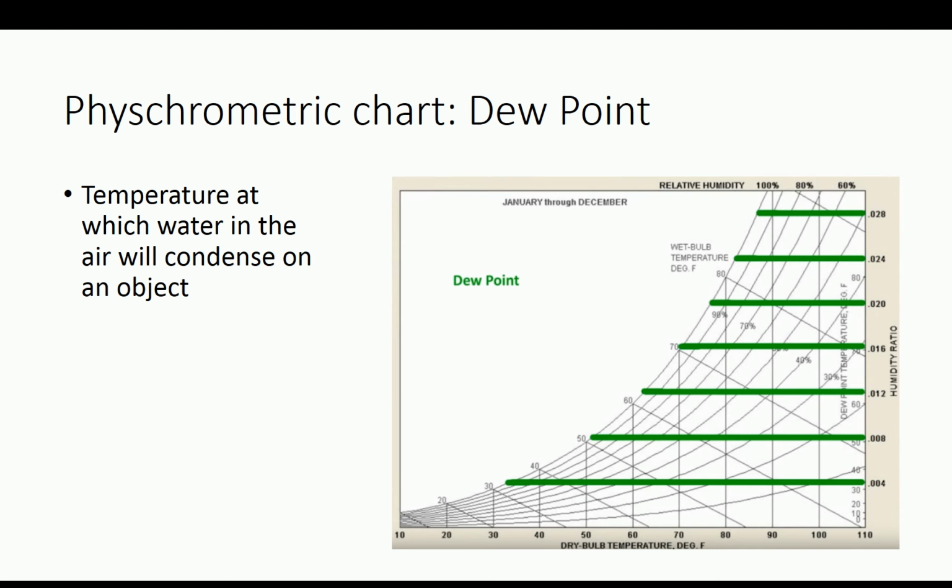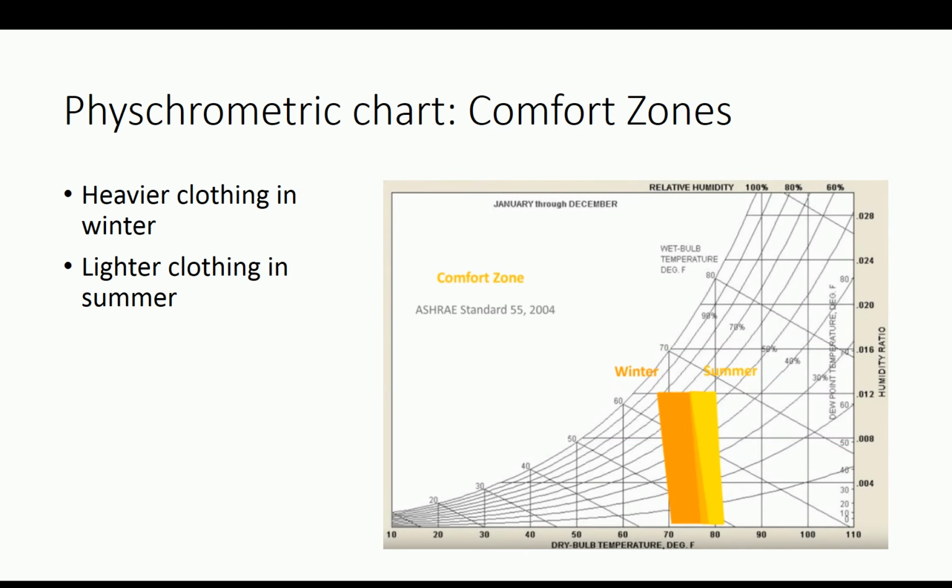Okay? All right, so I mentioned to you guys that we plot all of these things. I also mentioned that we can use the psychrometric chart to plot the comfort zones. So here is an example of two comfort zones superimposed on each other, laid on the psychrometric chart. So notice that these two comfort zones happen to be between 70 and 75, right? Or 78. And maybe they go down from about 76 to 82. I call BS on that, but whatever. That's somebody's model. Some skinny little person that doesn't get hot created that model, right? And take a look at how it slants over based on the humidity, okay? So there is a big difference between what you're comfortable in at one humidity versus what you're comfortable at in a different humidity, okay?